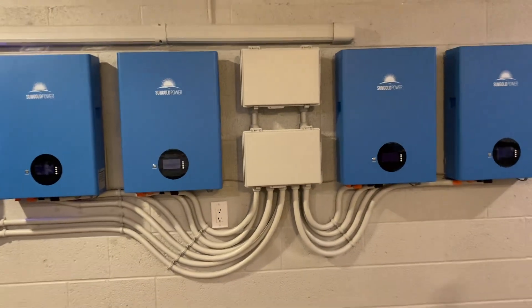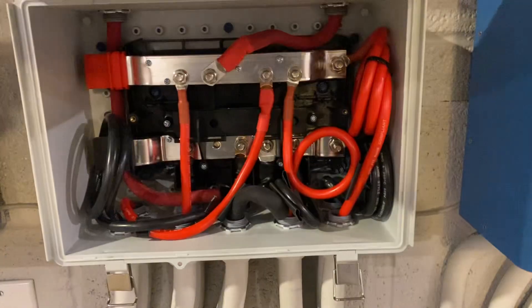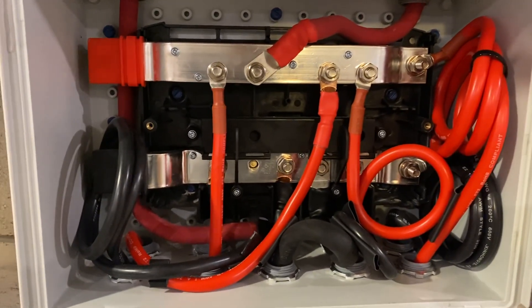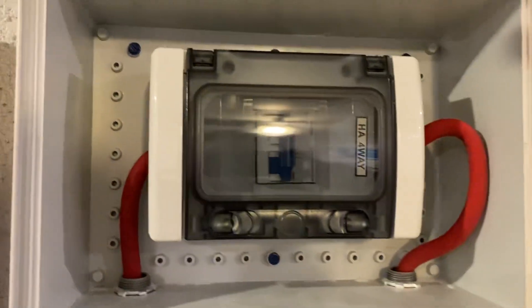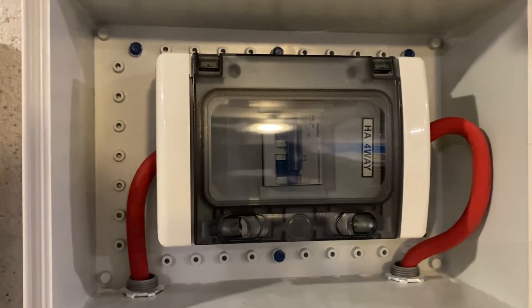If you want to run it temporarily and just chain them all together you can - maybe it'll work out for you - but what I ended up doing is running all the batteries to a Victron bus bar, the Victron PowerIn is what it's called. It looks a bit of a mess in here, but that's the Victron PowerIn with the cover off. All the batteries come back to this bus bar and tie in here.